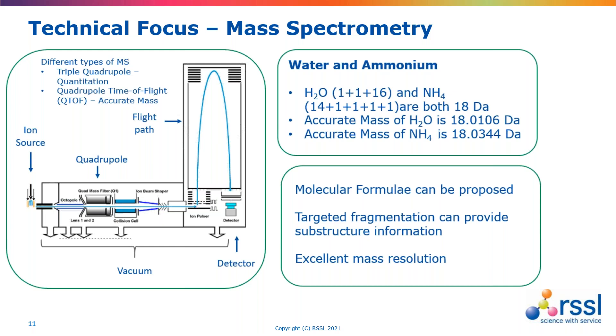The most important part within a QTOF is the time of flight. The system is designed such that we are fully aware of the distance of the flight path. Small mass-to-charge ratio ions follow that path very quickly, whereas larger ions follow it more slowly. Using calibrated ions and the simple equation speed equals distance over time, we are able to generate an accuracy of mass ions to as many as four or even five decimal places.